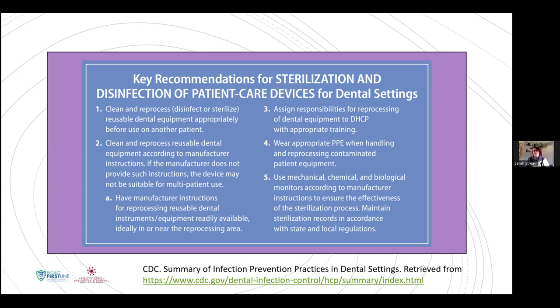Should also be assigning responsibility for that reprocessing to your staff. So who is responsible for it? And are you providing the appropriate training for them to be able to do it in an effective fashion? Should be wearing appropriate PPE, which includes our utility gloves when reprocessing instruments, and then also should be using mechanical, chemical, biological monitoring to verify our sterilization success.